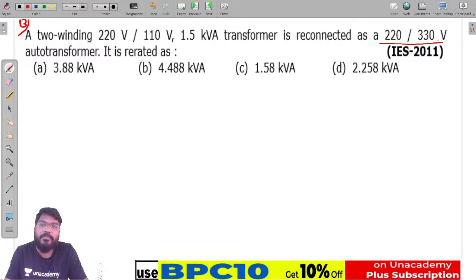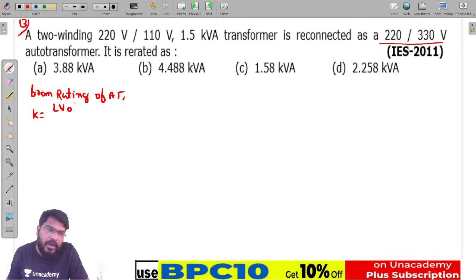We can find out very easily from the rating of the auto transformer. K is equal to LV of the auto transformer divided by HV of the auto transformer.